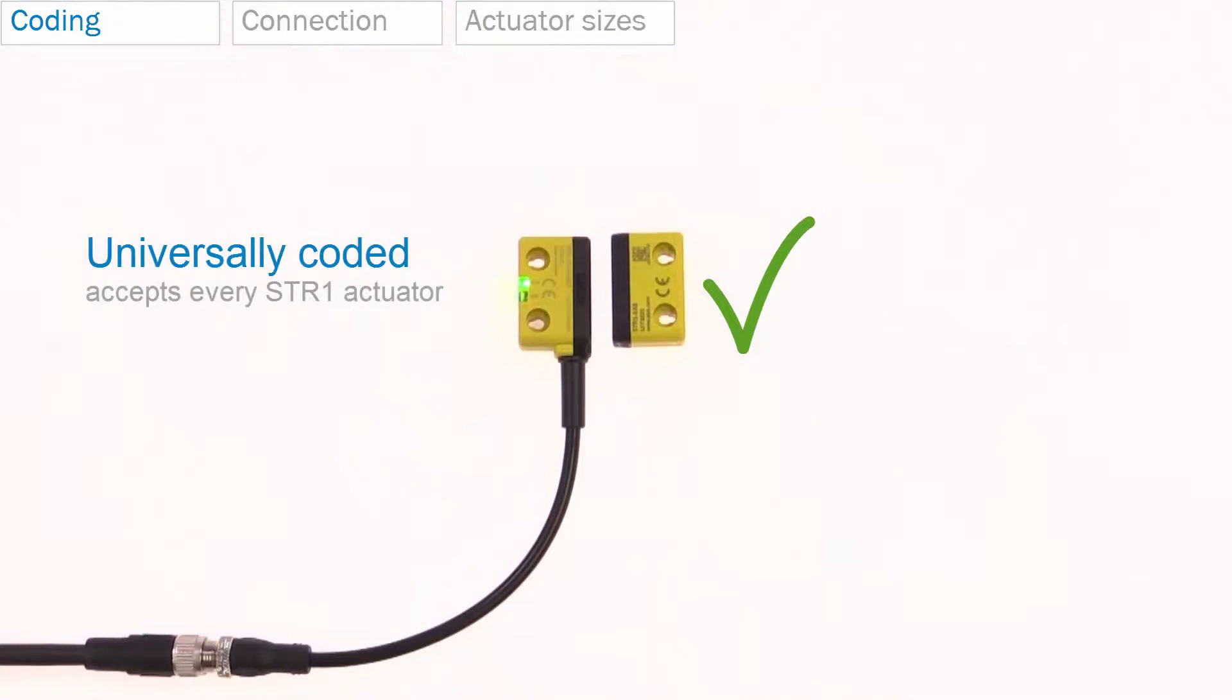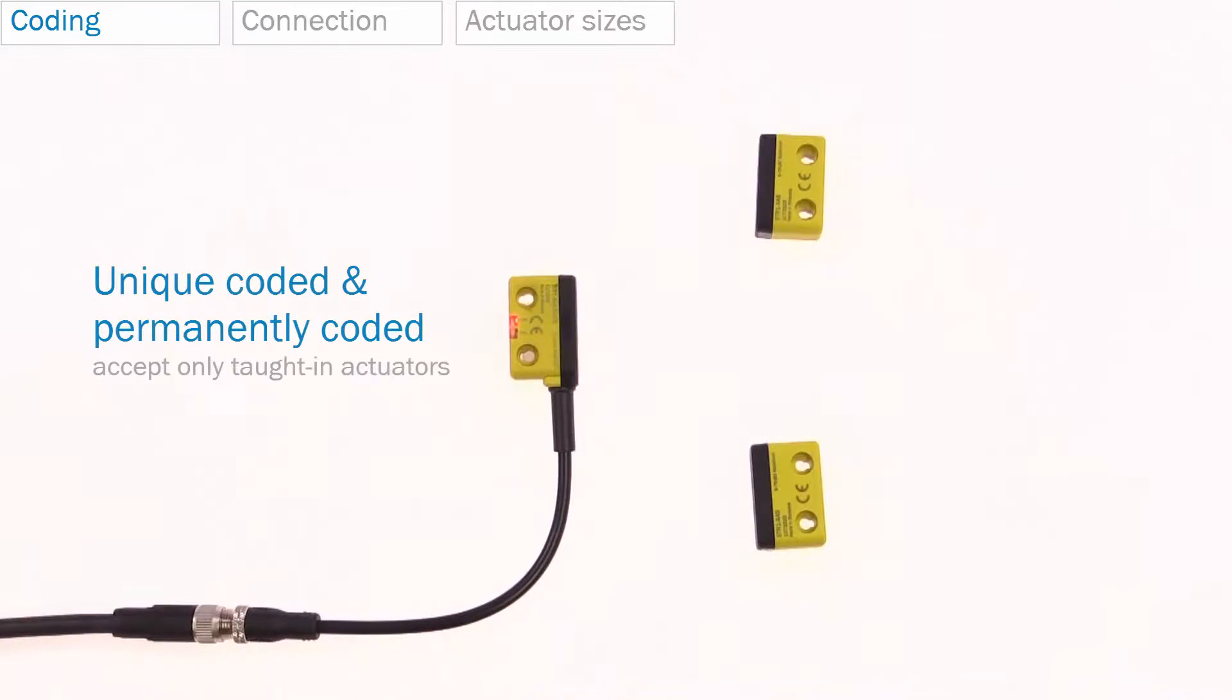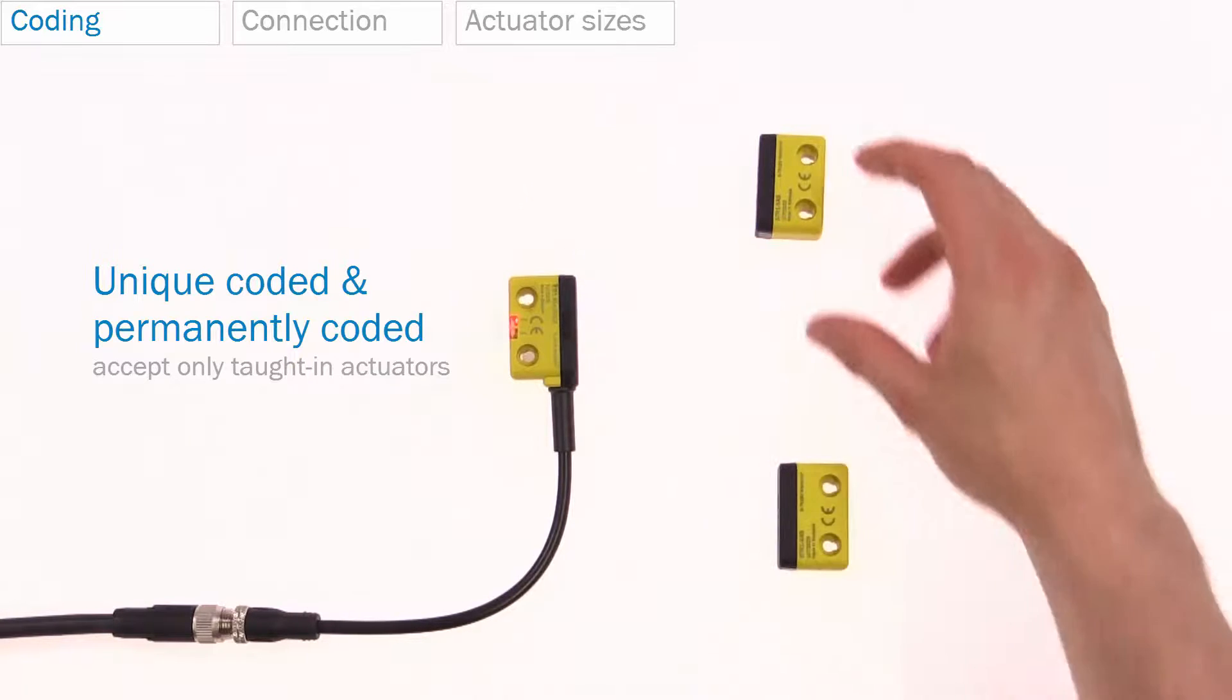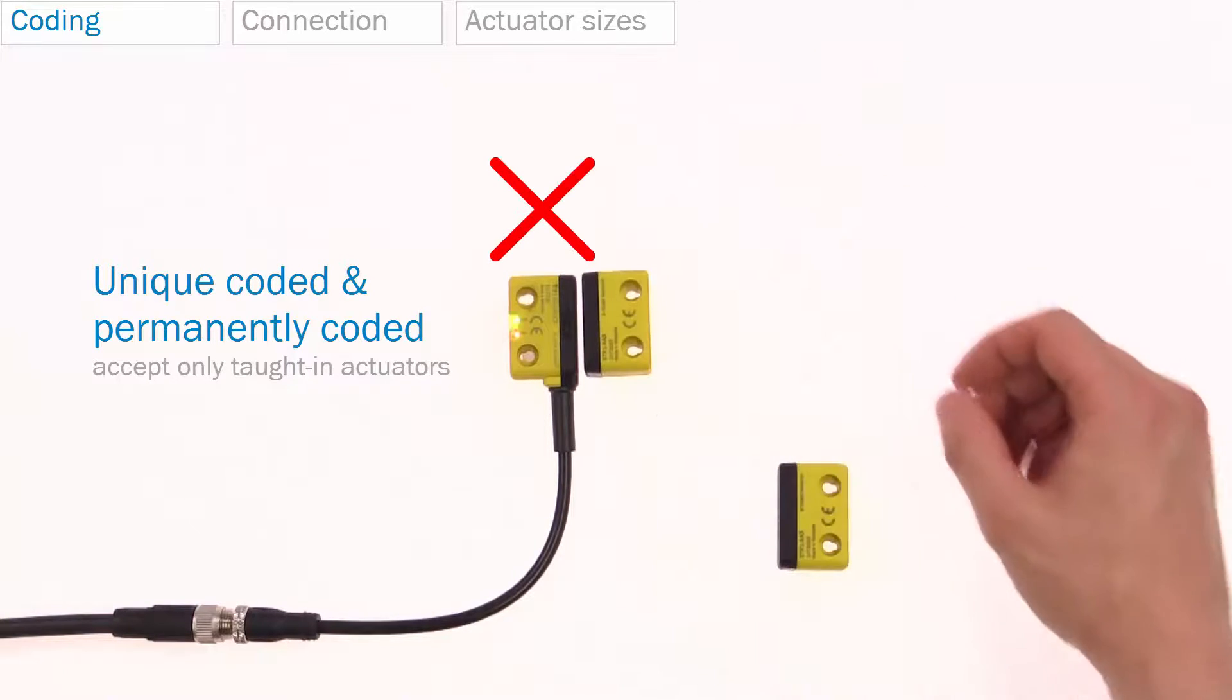Universally coded sensors accept every STR1 actuator. For applications that require a high level of protection against tampering, SICK offers two high coded versions: unique coded and permanently coded sensors. These accept only the taught-in actuator.